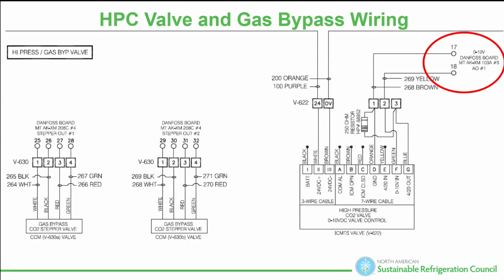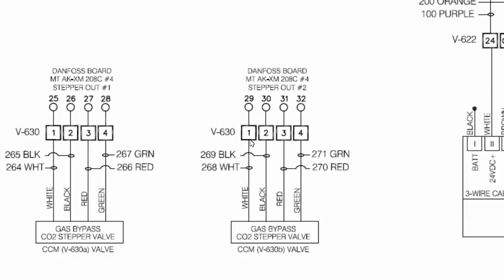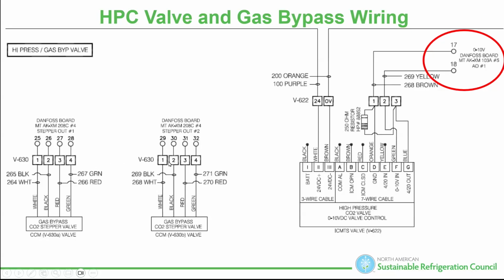You can take your meter, put it on DC, then take your leads and go to the white and black wire. We're all using white, black, red, and green. That's just the standard. I put my meter here. If the valve is energizing, working properly, and my controller is sending the proper signal, I'm going to see somewhere between -5 and -3 volts DC. And every time that valve moves, I will see it switch from negative to positive. -3, +3, -3, +3.